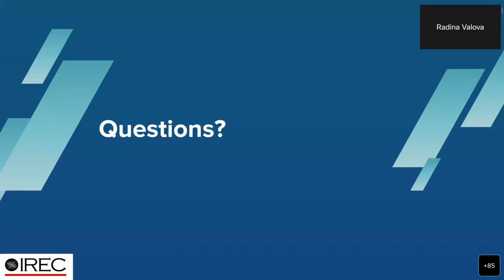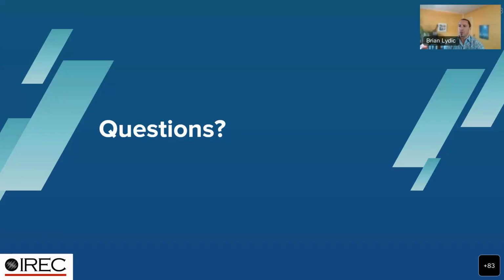That is, what times are acceptable for export cutoffs? This looks like it was directed to Brian during the UL 1741 section. Yeah, I can speak to that. So there's only a few jurisdictions that have really spoken to including power control systems in their rules as of yet - California and Hawaii, Illinois, and I believe Arizona and Maryland, maybe, but I can't recall off the top of my head if Maryland had actually put in a specific response time for inadvertent export.